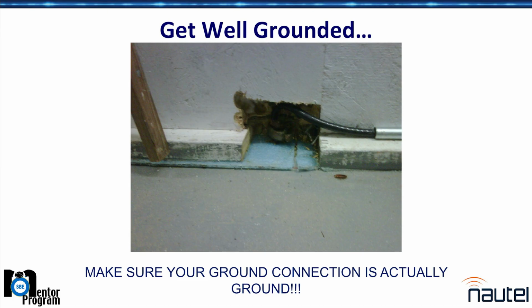Other thing you want to pay attention to is if you have to cut the footer plate from the building frame away to get to your ground rod, you're probably not connecting to a ground rod. That is the J-bolt that holds the building onto the concrete pad.